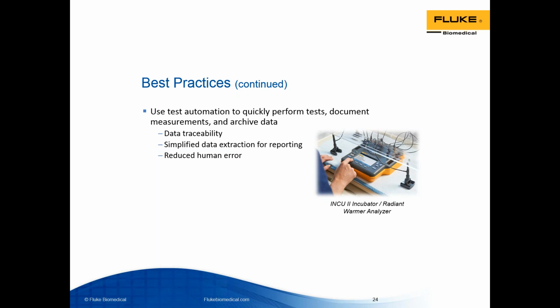INCU II analyzer. It's brand new, and using test automation with an analyzer can dramatically reduce the time taken for a test. So, for example, using the INCU II on the screen, once an incubator has warmed up, the INCU II can complete a test in just 15 minutes with the general testing feature. Its onboard automation will automatically run through the tests in both the standard and customizable test templates. So technicians will simply need to set up the device and start testing, and then you can walk away and are free to perform other work.